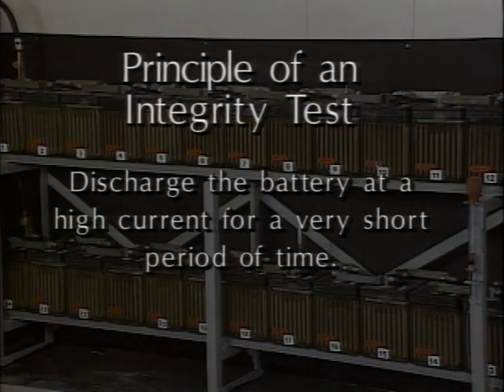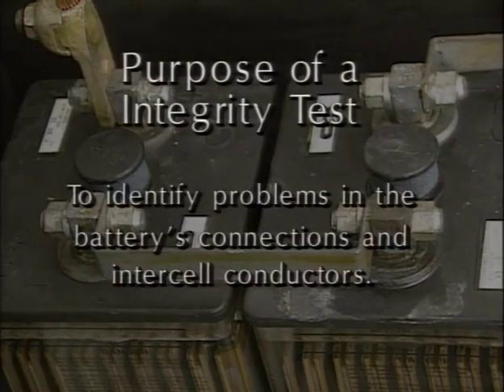The principle of performing an integrity test is to discharge the battery at a high current for a very short period of time. During this high current discharge, voltage drop is measured across each cell. The purpose of the integrity test is to identify problems in the battery's connections and intercell conductors.